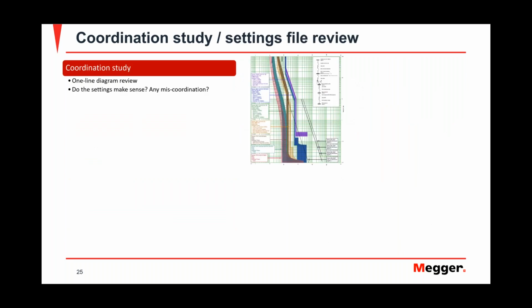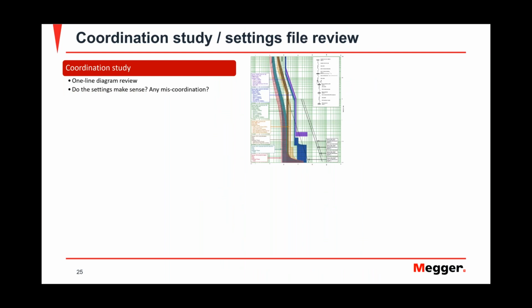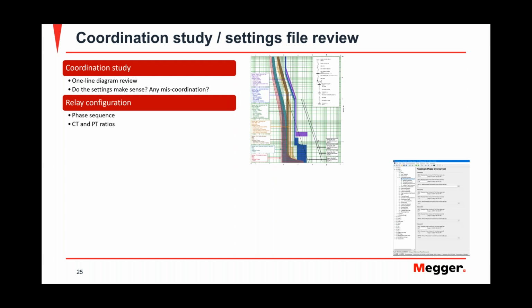If you have a chance to have a coordination study, usually they send you either a settings file or a coordination study. Have a one-line review. Do the settings make sense? When you look at the coordination, this is a miscoordinated curve. Did the engineer intend for this to be miscoordinated? Maybe this is a molded case breaker and the curve cannot change. Keeping those things in mind as you read the coordination study will allow you to understand the intention of the engineer.